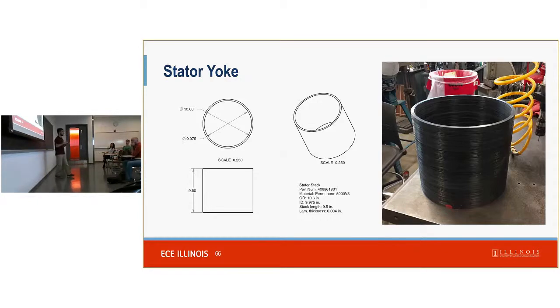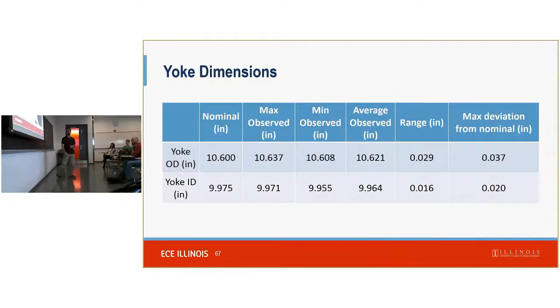Unfortunately, with this, as it's a stack of laminations, so thin layers all stacked and glued together, that stacking was not done as accurately as we would have liked, and so there was significant offset between layers. We can see about 37 thousandths of an inch on the outside diameter variation, which may not seem like a whole lot to us, but that's getting pretty close to the total thickness of the original air gap. And so that's very concerning, and we had to find ways to work around that.